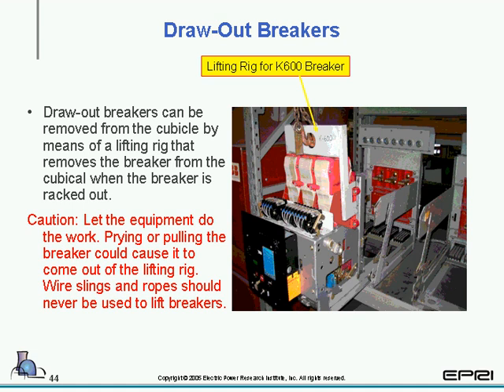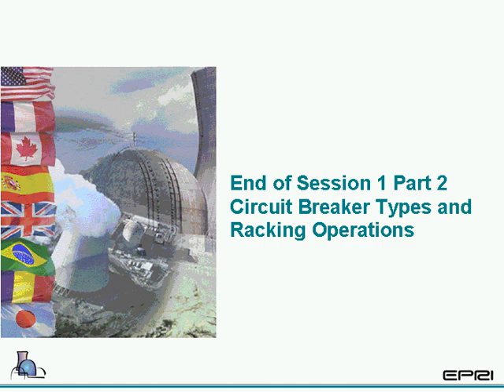And then draw breakers have some way of lifting them out of the cubicle, and normally into the frame or some sort of lifting rig. And caution, make sure you let the equipment do the work. Do not pry or pull on the breakers when you're removing them, or use wires or ropes and slings, because you could cause the breaker to come free from the lifting rig. That would be bad. All right, that pretty much ends Session 1, Part 2, Circuit Breaker Types and Racking Operations.